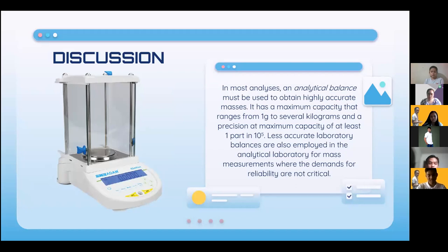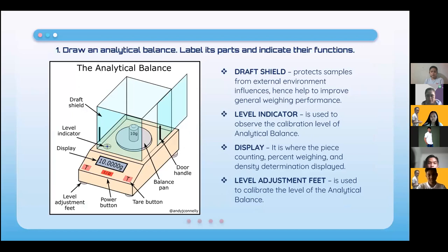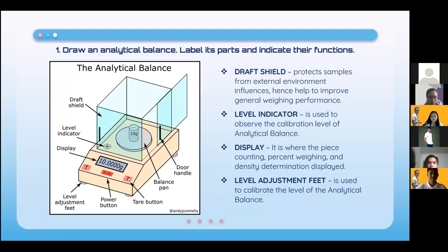In most analyses, an analytical balance must be used to obtain highly accurate masses. It has a maximum capacity ranging from one gram to several kilograms and a precision at maximum capacity of at least one part in 10 to the power of 5. Less accurate laboratory balances are also employed where demands for reliability are not critical.